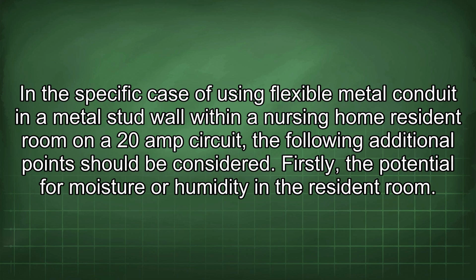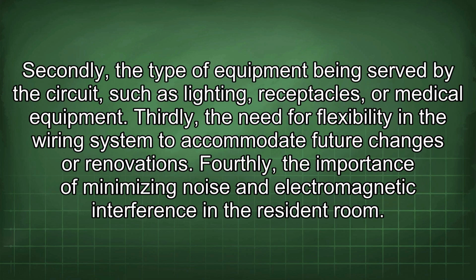In the specific case of using flexible metal conduit in a metal stud wall within a nursing home resident room on a 20-amp circuit, the following additional points should be considered. Firstly, the potential for moisture or humidity in the resident room. Secondly, the type of equipment being served by the circuit, such as lighting, receptacles, or medical equipment. Thirdly, the need for flexibility in the wiring system to accommodate future changes or renovations. Fourthly, the importance of minimizing noise and electromagnetic interference in the resident room.